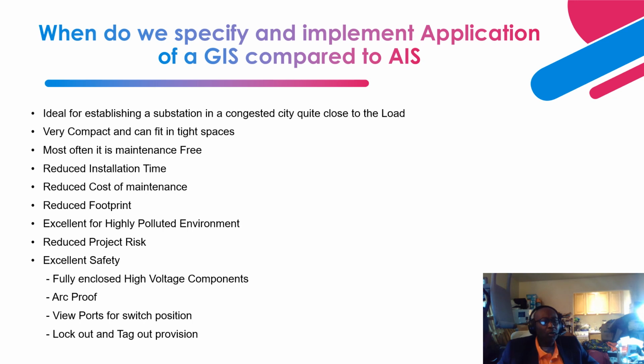Next is reduced cost of maintenance. Yes, and that is perfectly true. So for a GIS, if you follow the required maintenance and the required operation that is specified and delineated by the OEM, you will achieve a reduced cost of maintenance, because during the first 10 to 12 years of operation, most of the maintenance that you can perform is predictive maintenance, that is visual maintenance and data collection. And based on data from the cyclometer of the disconnects and the circuit breakers, and also information from the SF6 gas.